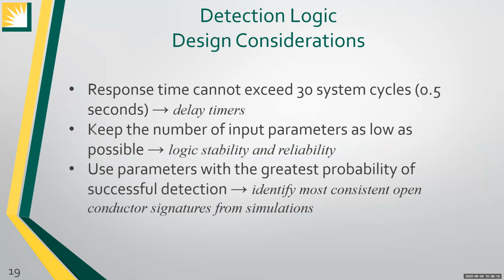To that end, there are a few key considerations the team and I had to keep in mind throughout the design process of the detection logic. Firstly, the response time of the detection logic could not exceed our detection time window. The greatest contributor to this restriction were the delay timers we used. Secondly, we had to keep the total number of input parameters as low as possible. This restriction was imposed mostly to ensure the detection logic was not so complex that it was unstable and unreliable. Lastly, we had to use parameters with the greatest probability of successfully detecting an open conductor. These parameters would be selected by analyzing the simulation data and identifying which behavior was most consistent throughout our simulations. Next slide, please.